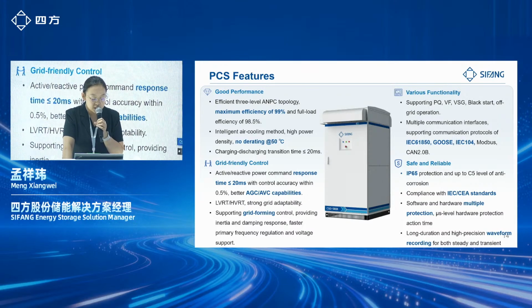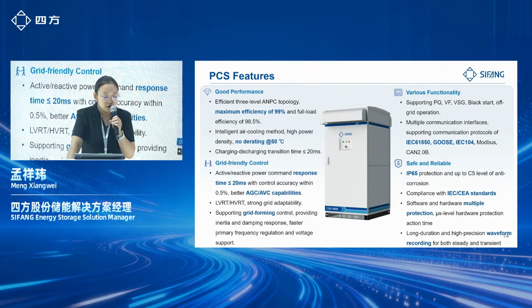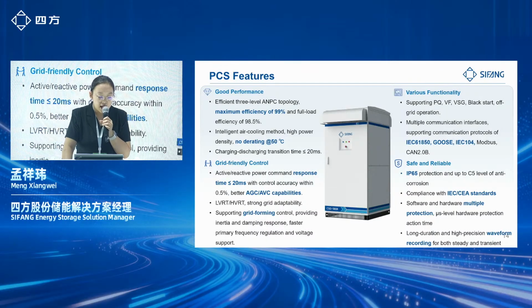The hardware protection action time can be less than 10 microseconds. We also use long-duration, high-precision waveform recording for both steady state and transient state, which makes maintenance easier. And we use an advanced software control method to realize high-speed control. The charging and discharging transition time, and also the active and reactive power command response time, are less than 20 milliseconds, which leads to better AGC and AVC capabilities for the BESS station.